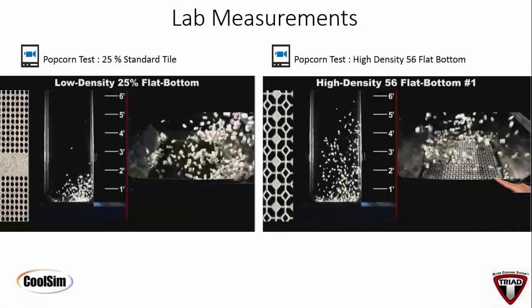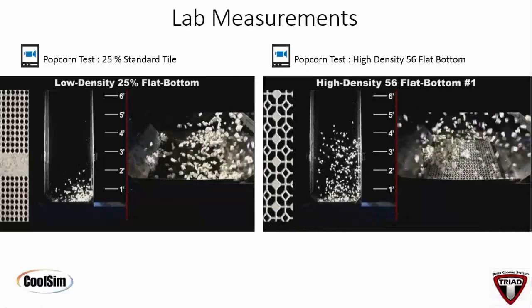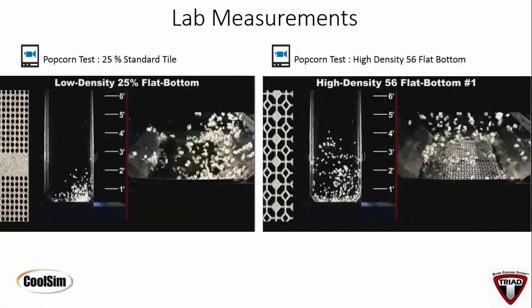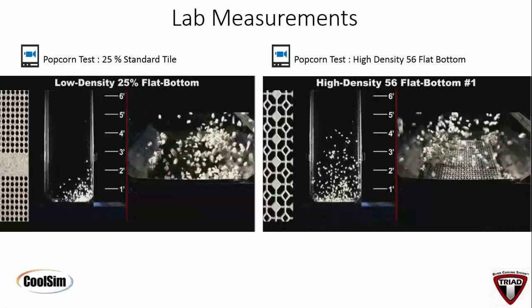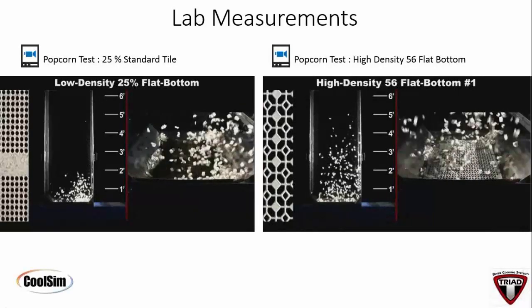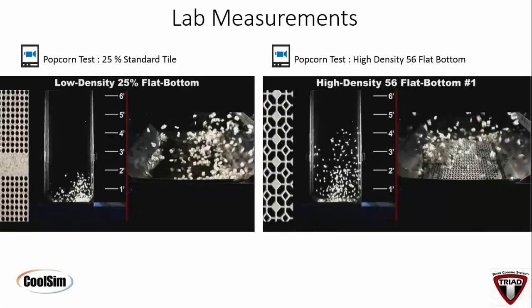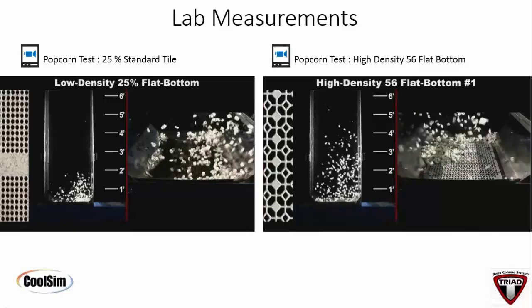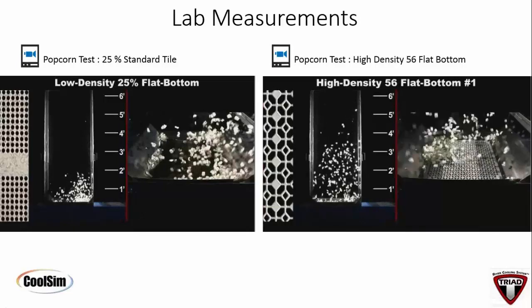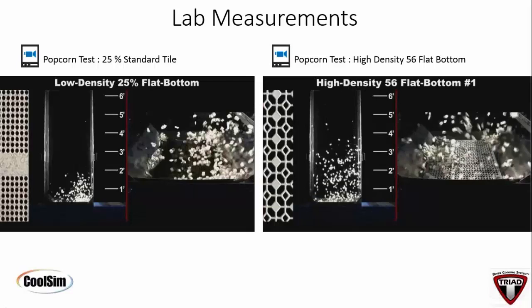Right. This is the 56 that we were looking at with the handheld anemometer testing. And again, it gets better stratification. It actually gets up to about 5 feet. But if you watch it as it moves, there's an acceleration back down to the front of the panel, which is that short cycle we were seeing with the handheld anemometer where it showed a negative 521 CFM. So we could physically see the flow of the air by using this popcorn analysis.